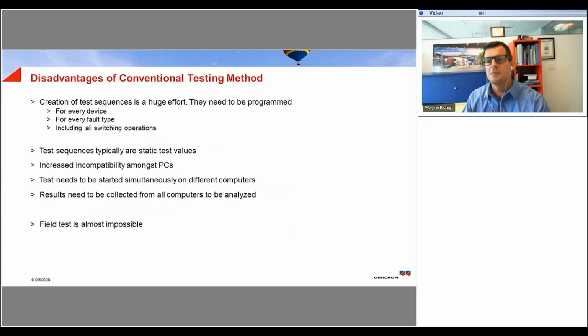So, some of the disadvantages of the conventional testing method. As previously described, the conventional method has proven to work well in labs. However, it comes with some disadvantages. The expected test values need to be calculated and programmed into a sequence for every single test device, which can be a very time-consuming process.